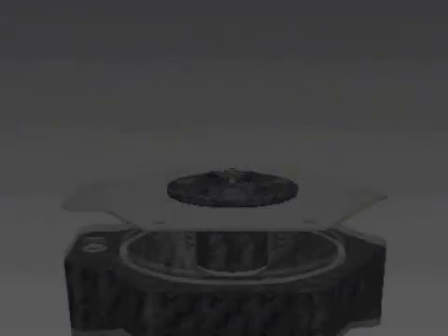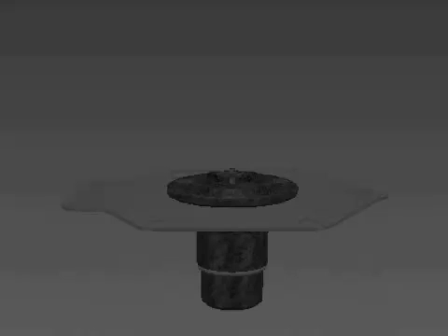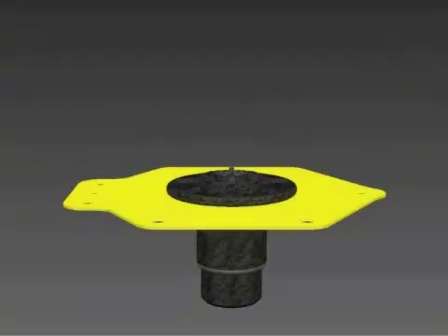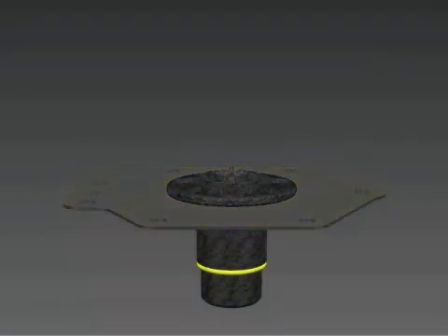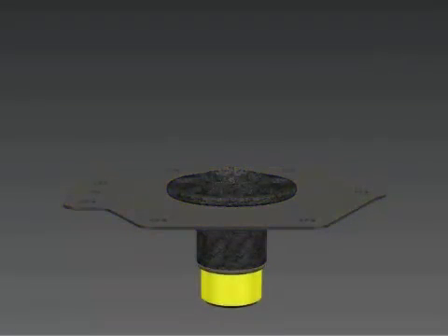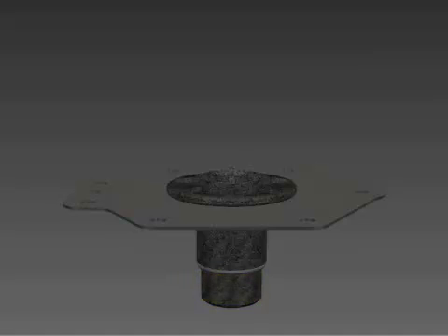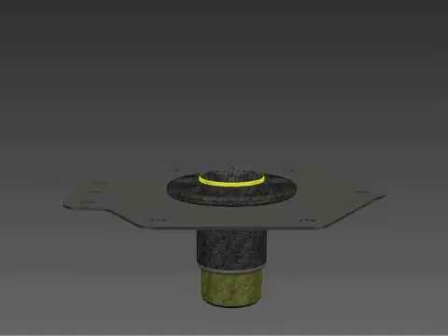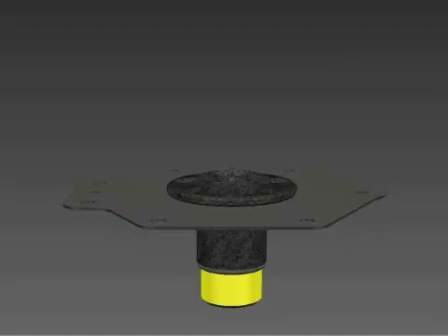Next, you will gently pull the cartridge from the relief valve cover. Inspect the diaphragm closely for wear or holes. Inspect the O-ring and surface on the plunger for any cuts. To replace the diaphragm, carefully disassemble the spring-loaded cartridge assembly. Be careful not to damage the seat edge or the O-ring surface of the plunger.